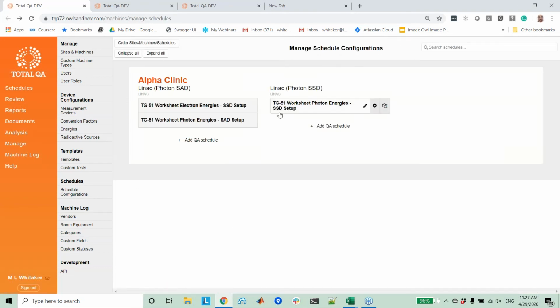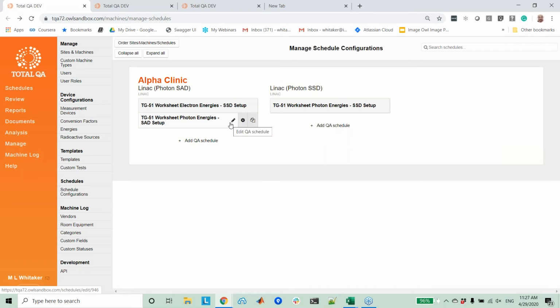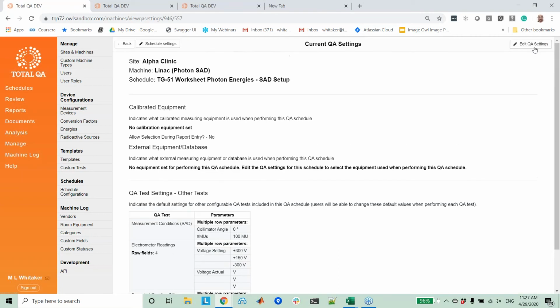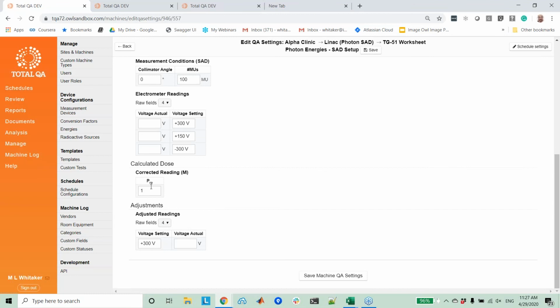So you could actually change this from schedule to schedule. And one place where you could even think about putting multiple different schedules is on the photons, where you have FFF beams, because one of the things you can set up ahead of time is this PRP factor. On the flattened beams, generally it sits at 1, but on the FFF beams, because you've got this drop off across the ion chamber there, generally that has to be changed.